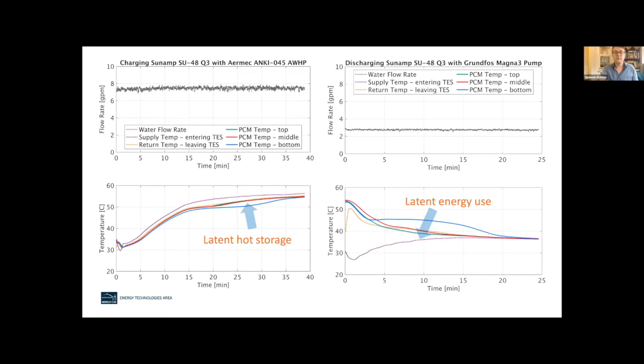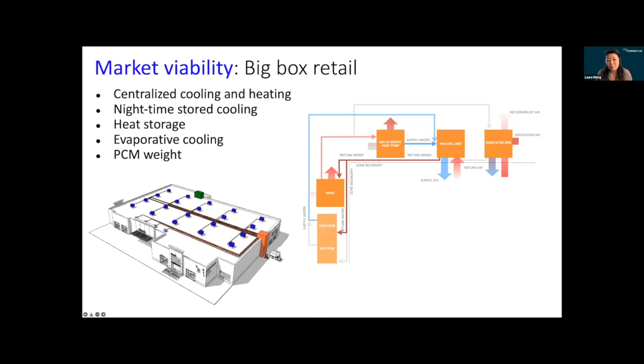I can talk a bit about some of the systems we looked at. One concept was for a big box retail store: you'd have either hot or cold energy storage, depending on the climate, potentially paired with an evaporative cooling unit, working together to provide chilled or heated water with glycol, distributed on the roof to smaller fan coil units. We'd put it on the side rather than the roof because of the challenge of the weight of the phase change material, so the weight is coupled to the ground here.